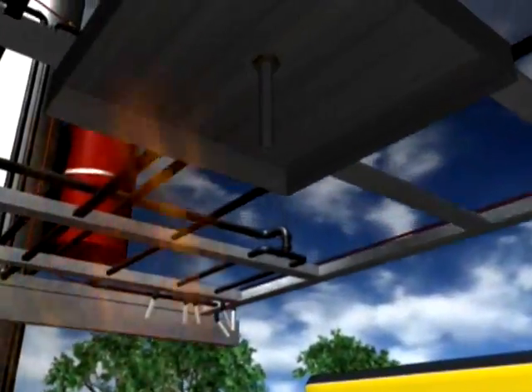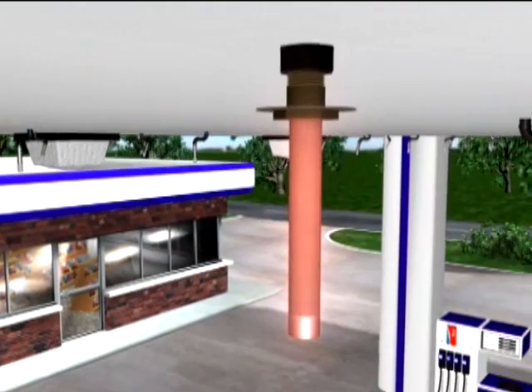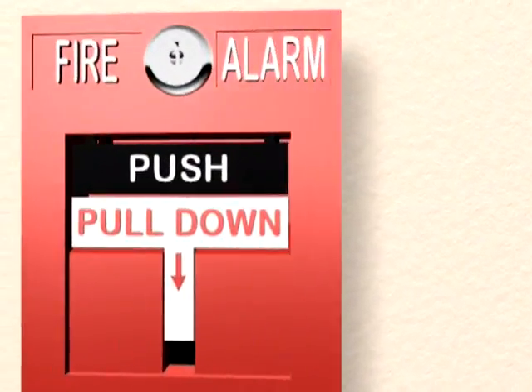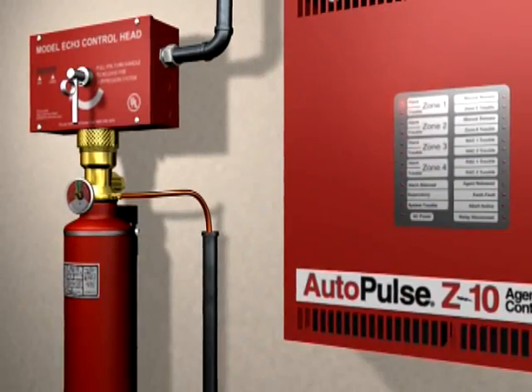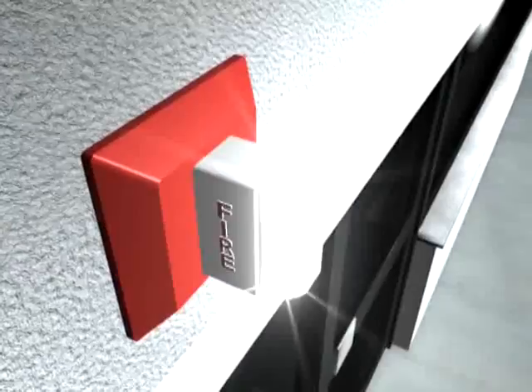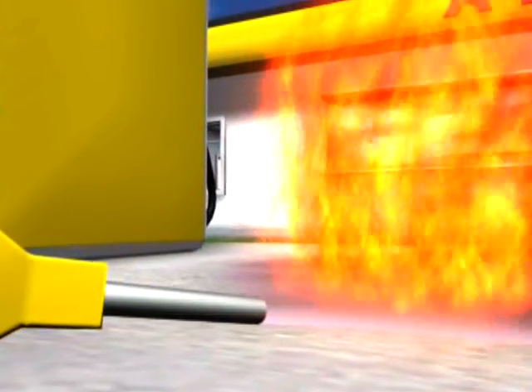When fire breaks out, the fire suppression system actuation is initiated either by the thermal electric heat detectors located below the canopy, or by use of the manual pull station. The manual pull station allows an individual to actuate the system manually from a safe, remote location. Either action triggers the releasing panel alarm, warning you and your customers. Simultaneously, a fuel pump shutoff switch is activated to discontinue the fuel supply.